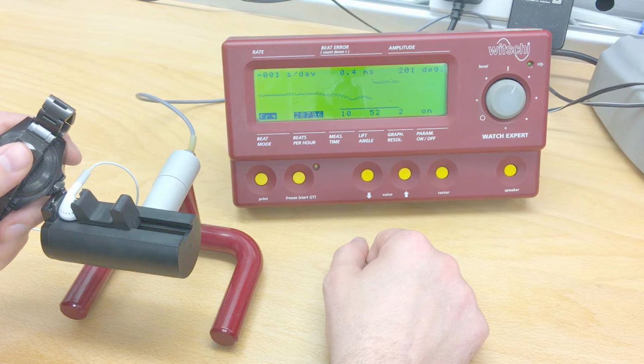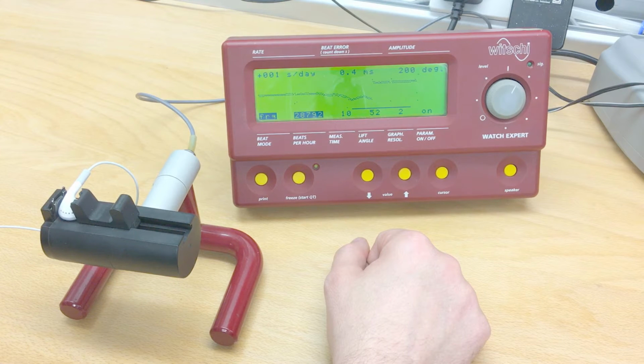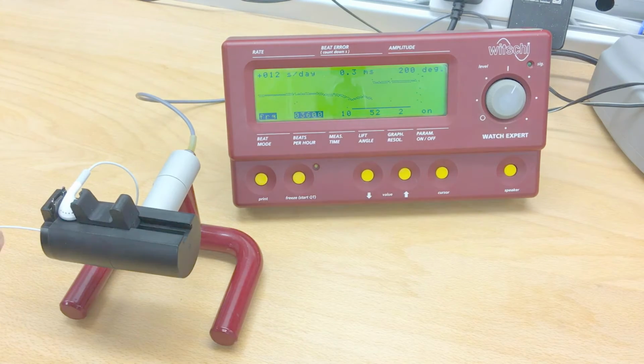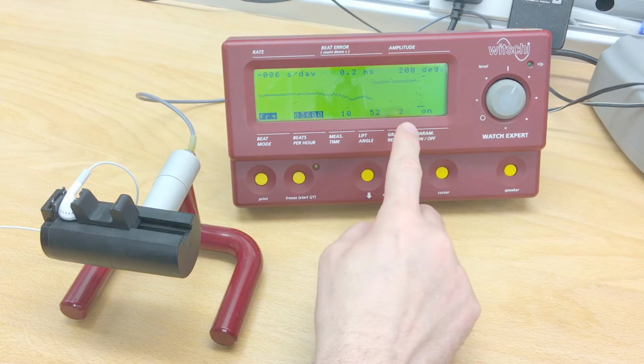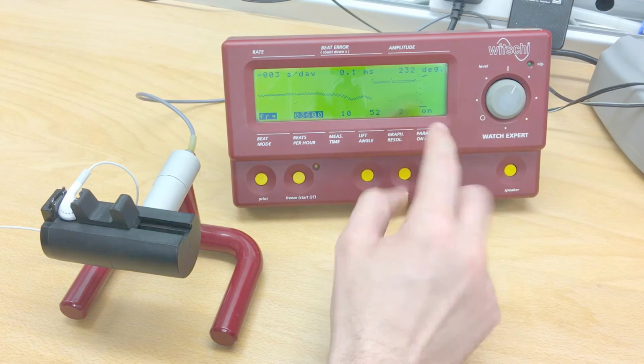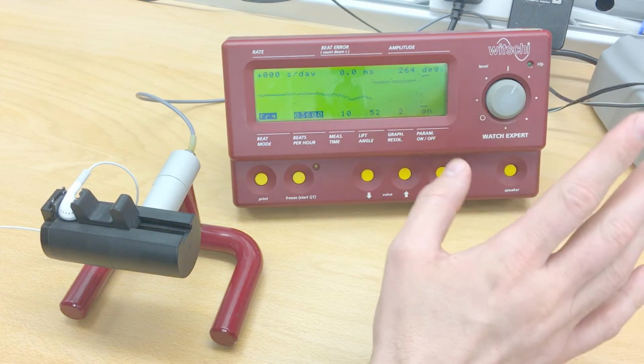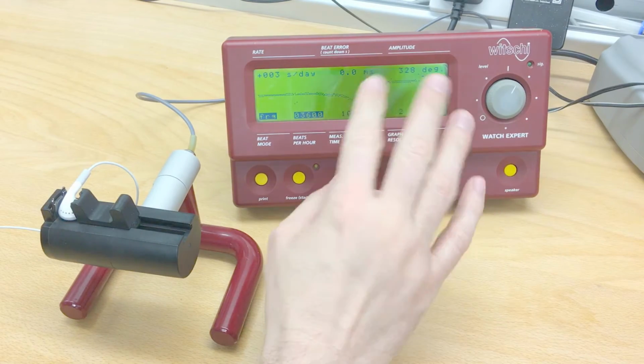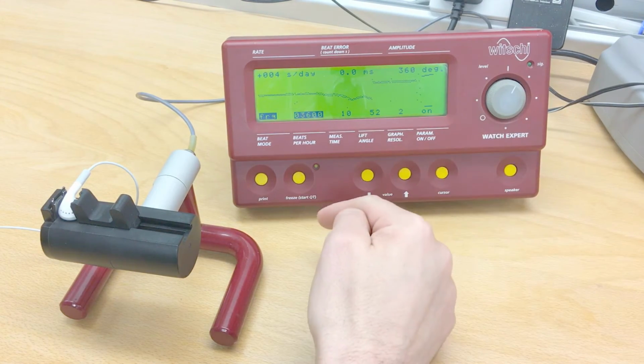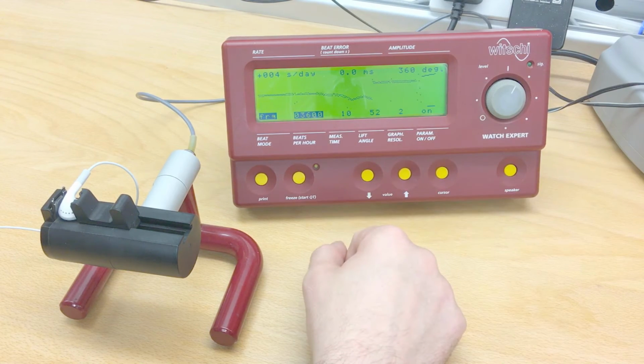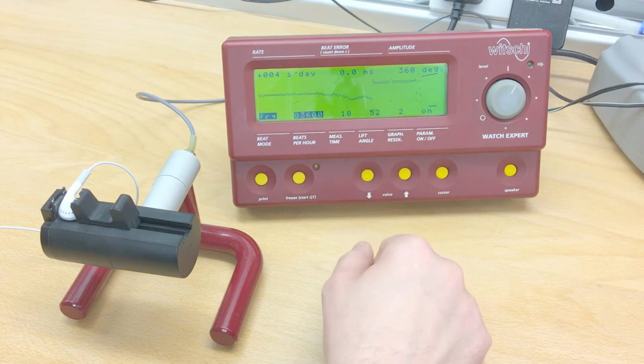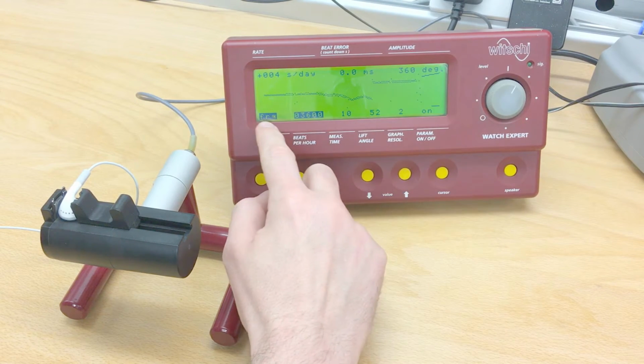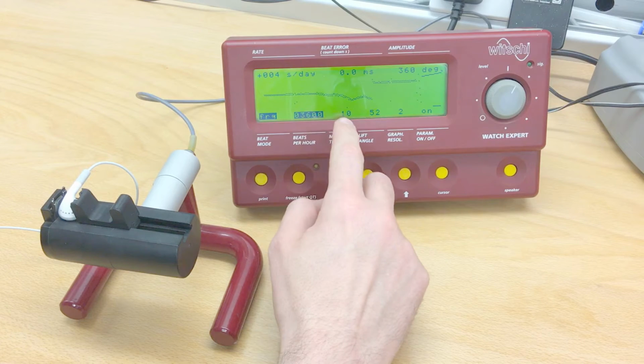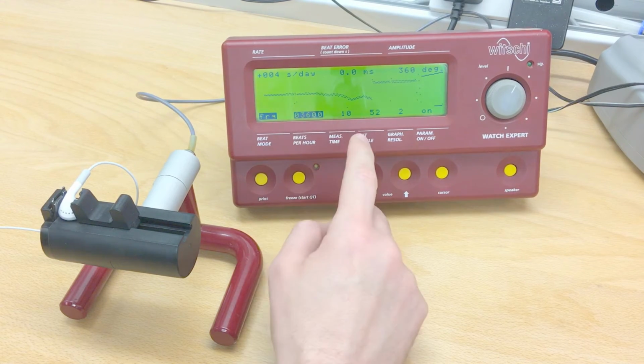Now, with as little noise and interference as possible, I'm going to draw the watch away. And yes, I was lucky I got it first time. Sometimes, if you pull it away at just the wrong moment, the machine loses interest. Maybe because there's too much of a gap between the next tick and it just stops listening. But if you time it just right, I would say halfway between the seconds, it'll carry on listening and it picks up those 1 seconds. And you'll see there's a little bit of noise. Sometimes that noise carries on for 10 seconds or more before the machine works out that it's now listening to a different frequency. In fact, I'll just start it over.